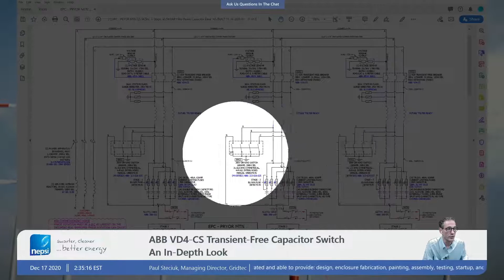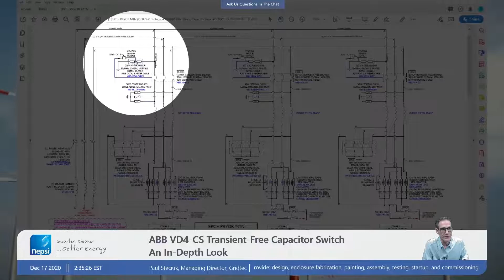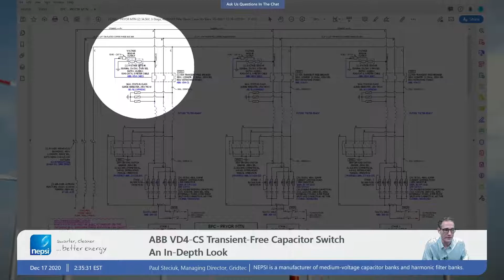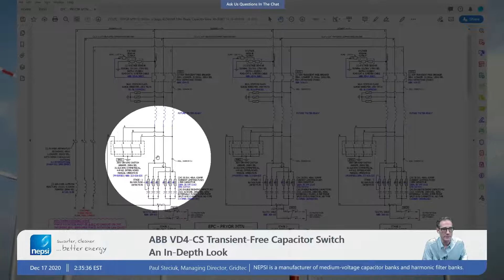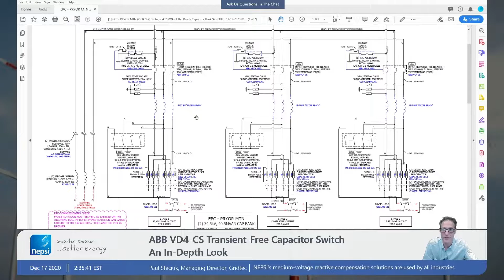First thing to note is there are no transient inrush reactors. That's the cost savings there. And the other thing to note here is we have a voltage sensor on phase A. And that voltage sensor is on the line side of the VD4. That's the first thing to note. And the other thing to note is it's an ungrounded Y cap bank here. So I'm going to flip over to the next page where we can show the control drawing here.